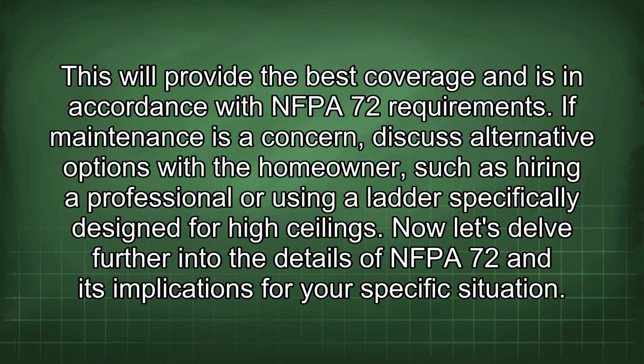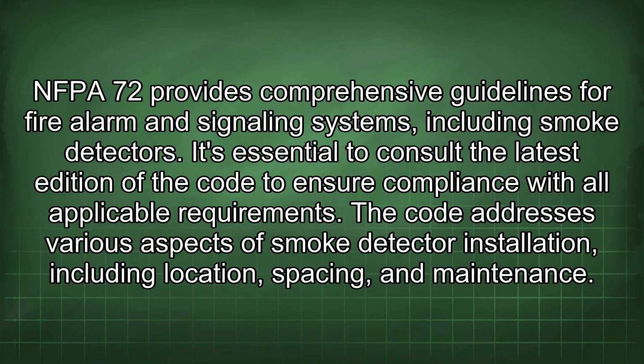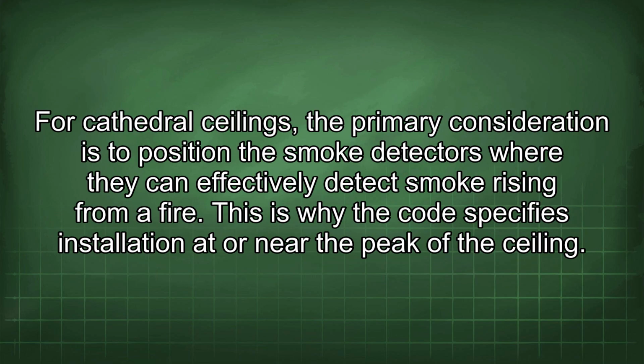Now let's delve further into the details of NFPA 72 and its implications for your specific situation. NFPA 72 provides comprehensive guidelines for fire alarm and signaling systems, including smoke detectors. It's essential to consult the latest edition of the code to ensure compliance with all applicable requirements. The code addresses various aspects of smoke detector installation, including location, spacing, and maintenance. For cathedral ceilings, the primary consideration is to position the smoke detectors where they can effectively detect smoke rising from a fire. This is why the code specifies installation at or near the peak of the ceiling.